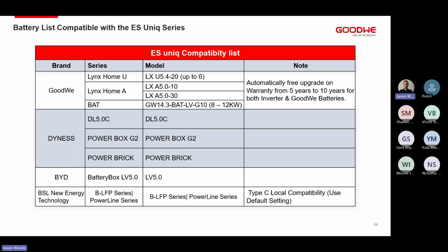And what that means is when a battery manufacturer from a local area wants to become compatible with the inverter, we will send them an inverter and our default protocol, and they will cross-match their battery's firmware or battery protocol to match our inverter. So when we configure the system, you will not necessarily see that battery's name. You will connect to our default protocol. This list is available through our distributing partners or through us directly at GoodWe. You can get in contact with us and I'll be able to share it with you, or get in contact with our service team and they'll be able to share it with you as well.